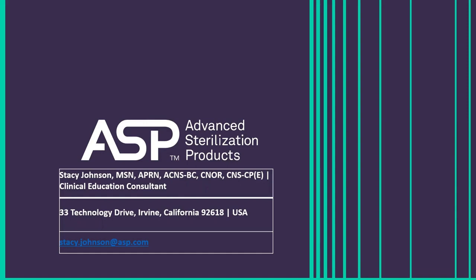AAMI recommends that cleaning verification of flexible and semi-rigid endoscopes should include visual inspection combined with other verification methods. So including a true visual inspection in your processes is important, and that's to try to assess both external surfaces and internal housing and channels. So working in multidisciplinary teams in an organization and looking at policies and procedures and trying to determine what the best practices would be to institute those kinds of tests, and using instrumentation like a borescope, is certainly important. But as far as cleaning verification tests, common markers include protein, carbohydrate, hemoglobin or blood, and ATP. So those are cleaning verification tests and kits that are available on the market.